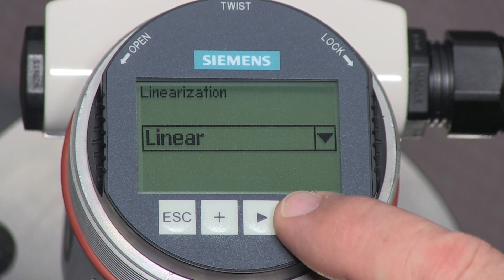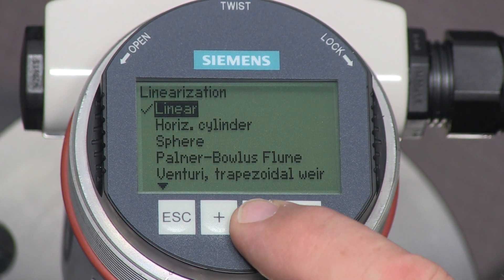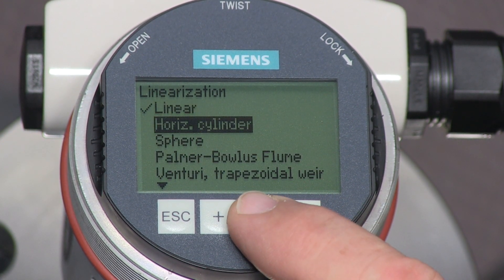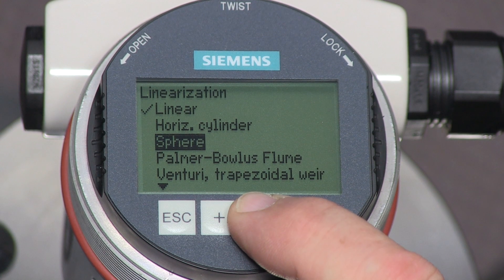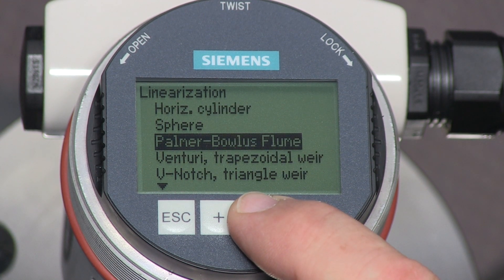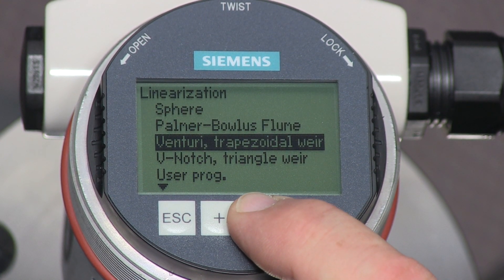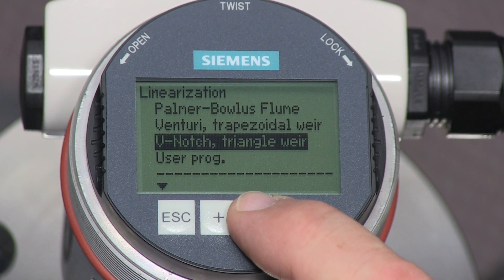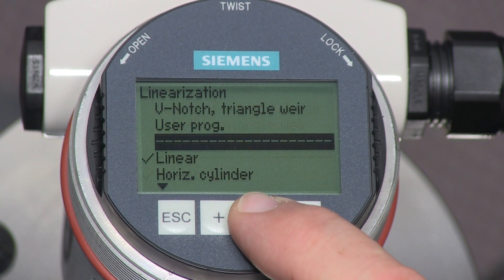Changing the linearization parameter is required when measuring volume in a horizontal or spherical tank. We will leave the LG 250 set to linear.